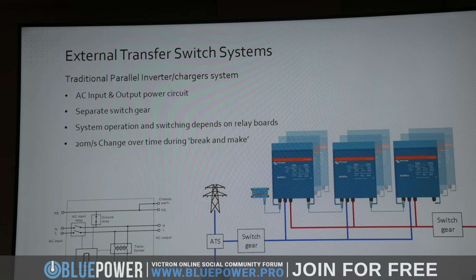This is 400 amp - not available for Quattros. It's not that you need it, it's that in the absence of the external transfer switch, you're relying on potentially 16, in the case of the Multiplus 5kVA, maximum 12 of the individual relays, which are electromechanical, to all close or open at exactly the same time.